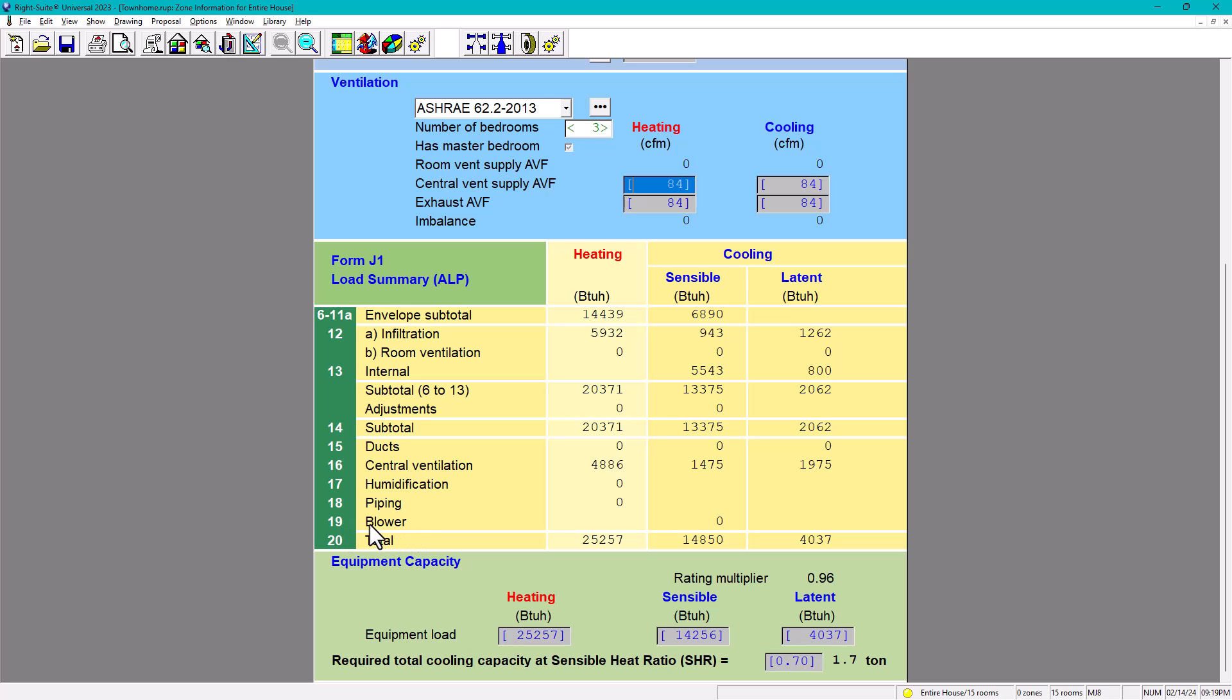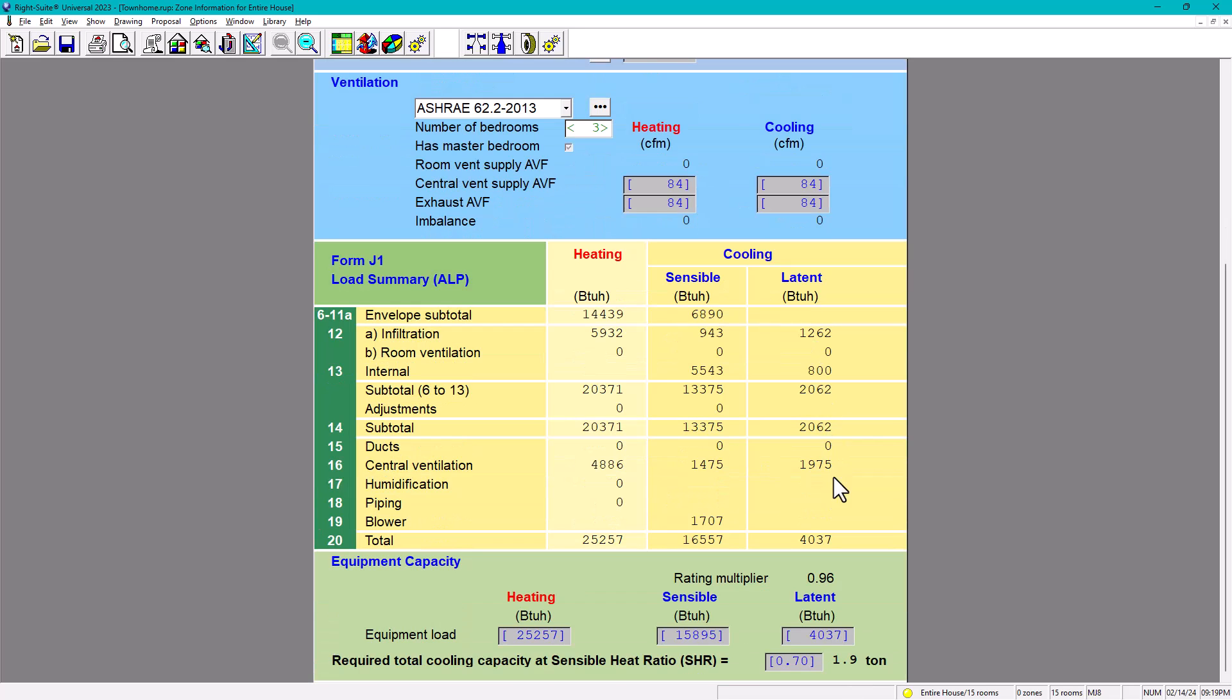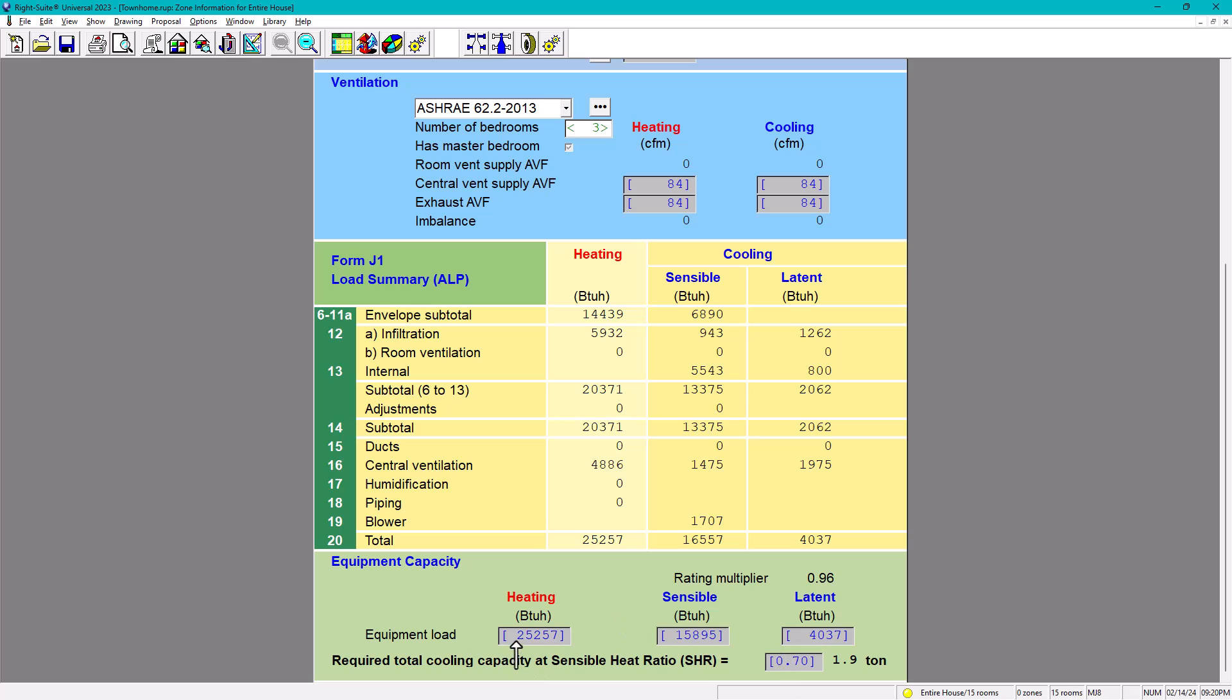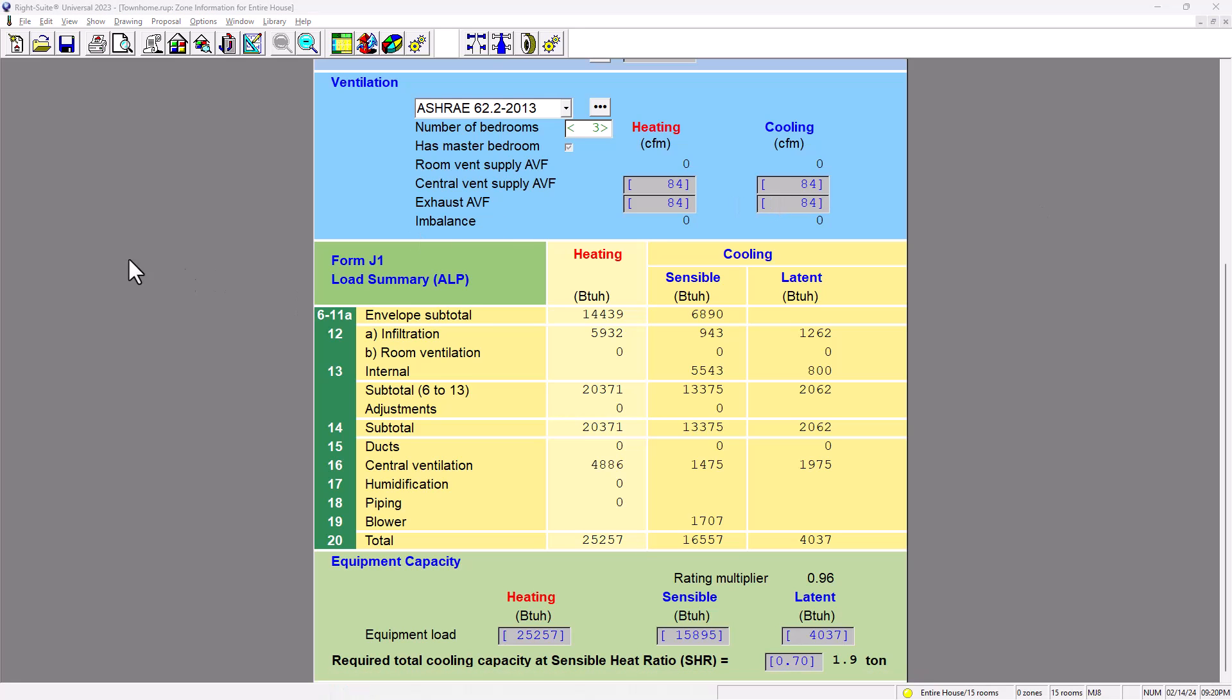Now, here is the thing. Blower. This is the blower data, this is the equipment. And again, you can always press F1. As of now, it's looking like it's 1.7 ton. That's my load for the system. The system that I need is 1.7 ton. I would get a two ton unit. However, let's check on the blower data, how much it increases. It's 1.7 ton. So we're going to go here, blower data, check that. And it says 1.9 ton. See how much it increases? Now, I was telling you, because when you're a designer, sometimes you have to be effective. You don't have to overthink like, what is this, what is that? You're wasting a lot of time. So that now in your free time, of course, you can do some research. Let's take a picture. I'm going to put this to the side. I already took a screenshot of these values.